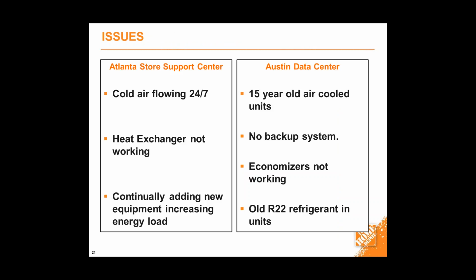Some of the issues we encountered when we started researching these centers in Atlanta, the Store Support Center: in the data center, 39,000 square feet, cold air was flowing 24/7 without regulation. Our heat exchanger wasn't working either, and they were continually adding new equipment, increasing the energy load all the time. The layout of the equipment was haphazard, units facing different directions, cold facing hot. They just put units wherever they found a slot.